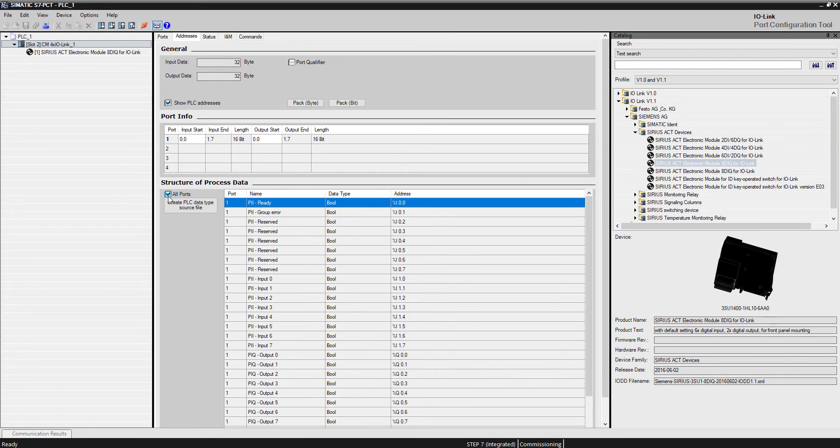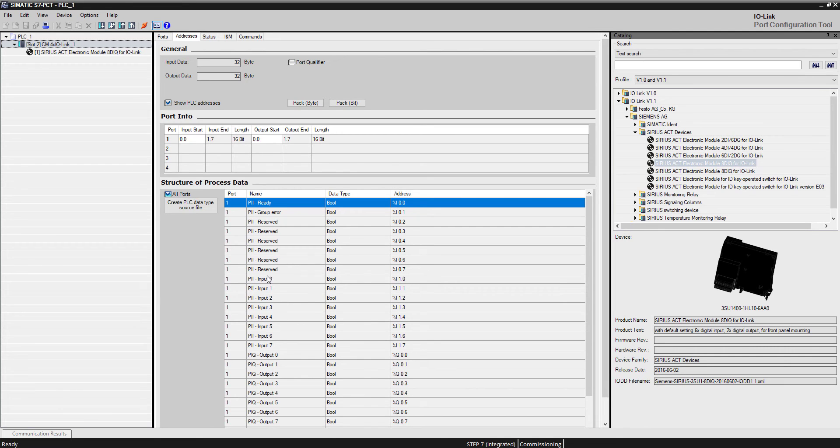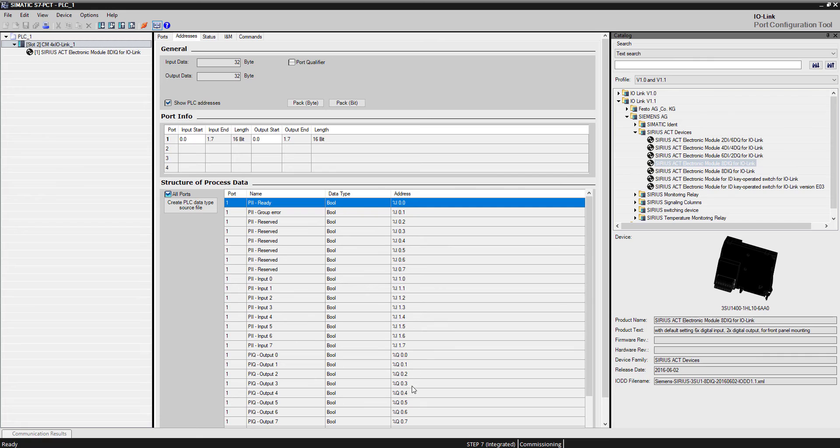This gives you detailed information about the signals, both input and output, and status signals that are available via IO-Link. Not only the signal name, but what actual PLC address it is specifically assigned to. So you don't have to open up a manual or anything to say, okay, I want to look at the four input signals. They're going to be starting at input 1.0 and going to input 1.3. And on my output signals, those first four are going to be output 0.0 going to output 0.3.